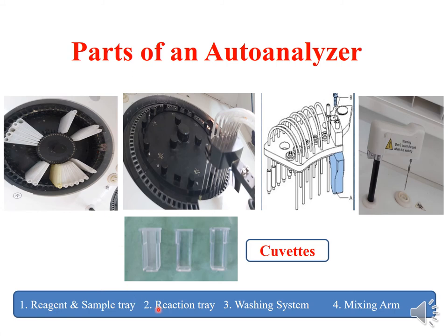Along with this wheel, there is a second wheel known as the reaction tray. In this reaction tray there are slots for a large number of cuvettes in which the reaction will occur. This is how the cuvettes look, and there are two robotic arms — the reagent arm and the sample arm.